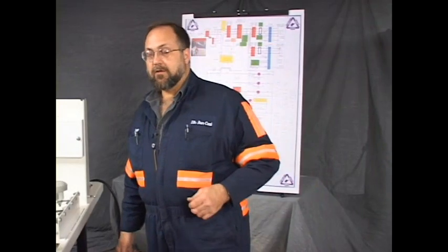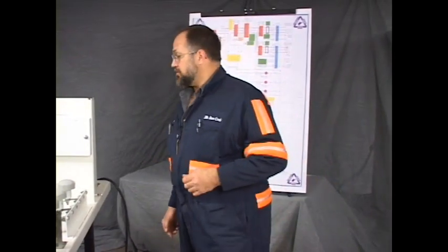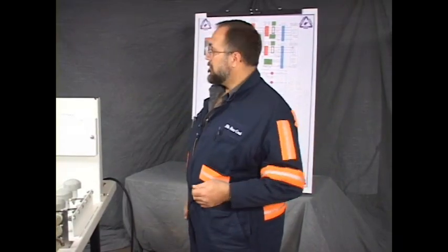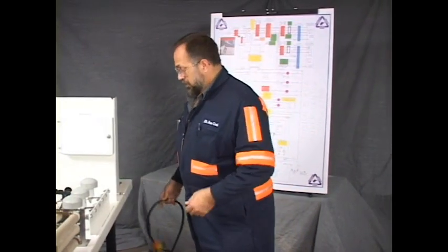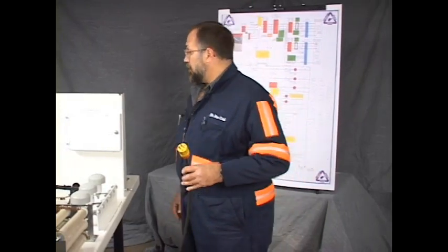Okay, fellas, as with anything that you would encounter underground, the safest possible way to troubleshoot any electrical circuit is with continuity tests with the power off. You can do some troubleshooting, no repair work with power on, but it's safer by far. Anything that can be troubleshot without power should be. That's best. So this box is powered by a 120 volt power supply, plugged into a normal wall outlet with this cord. This is the cord for the box.